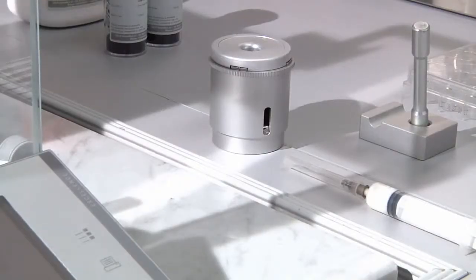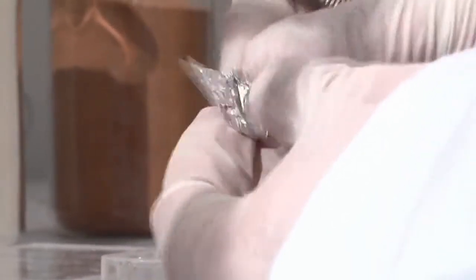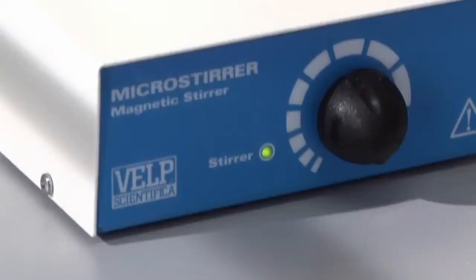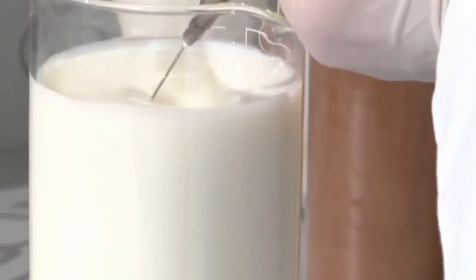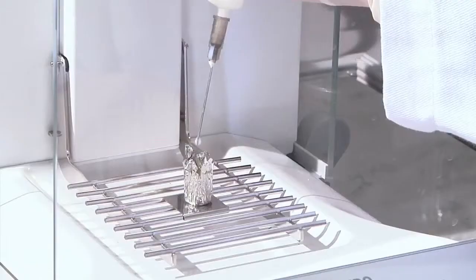Dedicated accessories simplify the sample preparation and are ideal to improve the flexibility of the instrument. In the case of liquid samples, the sample preparation procedure remains very similar, with the only addition of an inert material.